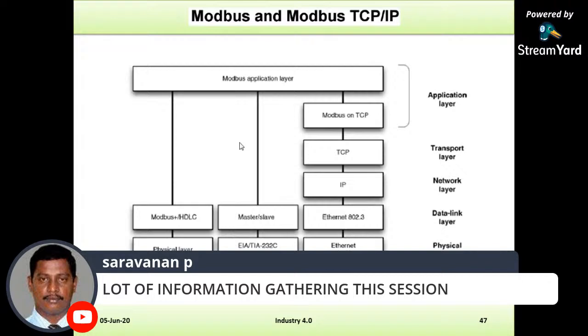So variations are available. If I'm going to connect the physical layer, then there we use serial communication like RS 232 protocols, and another is RS 485 protocols. And the second one is the data link layer. At the moment, we are going to utilize Modbus with the help of a master and slave arrangement. Our client server architecture will be here.